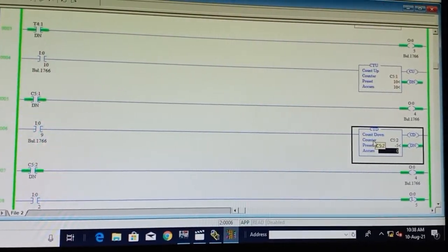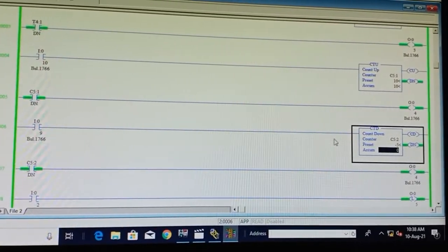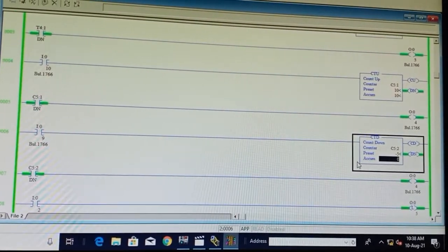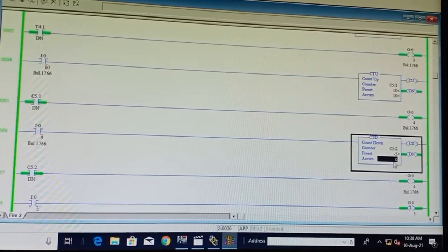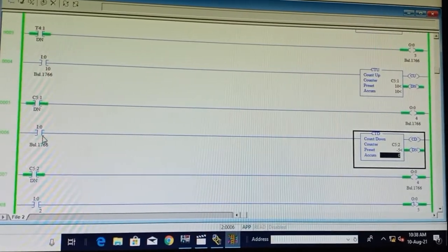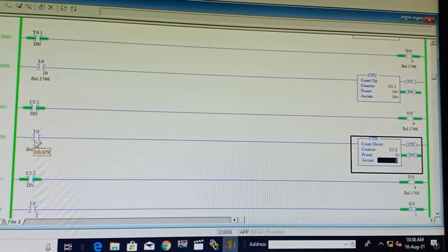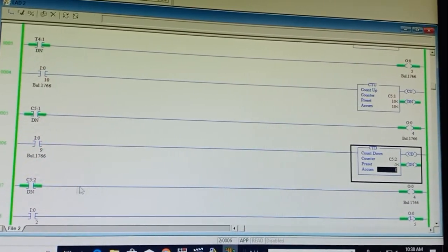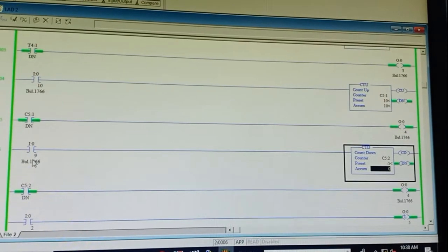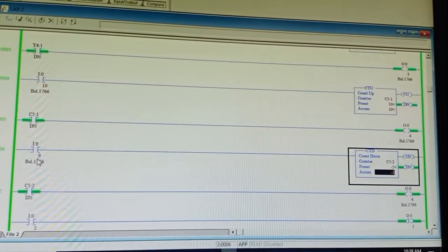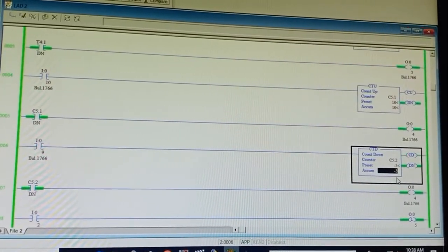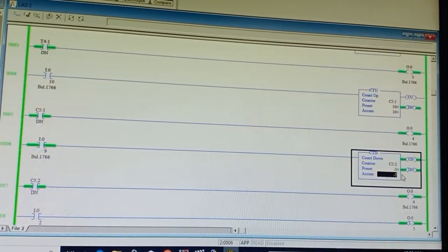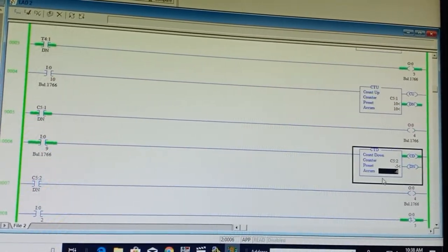For down counter, the preset value counts in decreasing order. Preset value is minus 5, current value is 0. As we toggle switch I9 (address I:0/9), each press decrements: minus 1, minus 2, minus 3, minus 4, minus 5. After reaching minus 5, the done bit turns on. Rahul presses I9 — it counts minus 1, minus 2, minus 3. You can also see the CD enable bit is on.